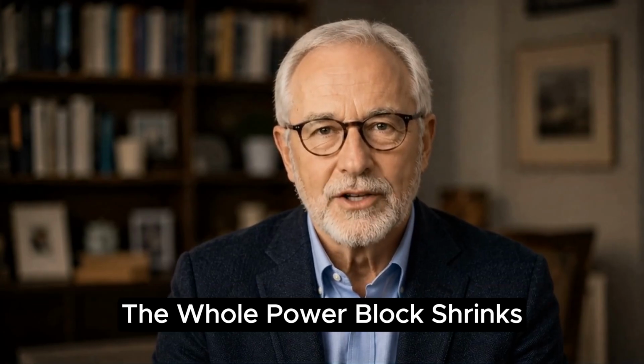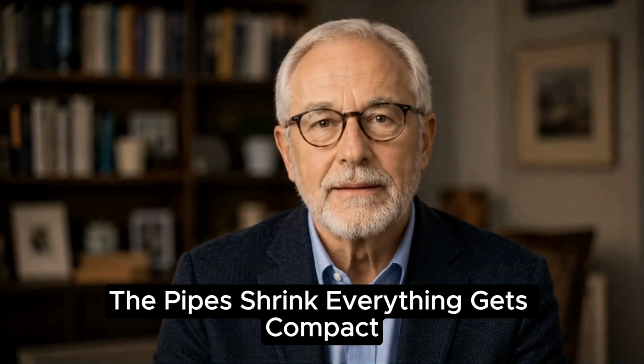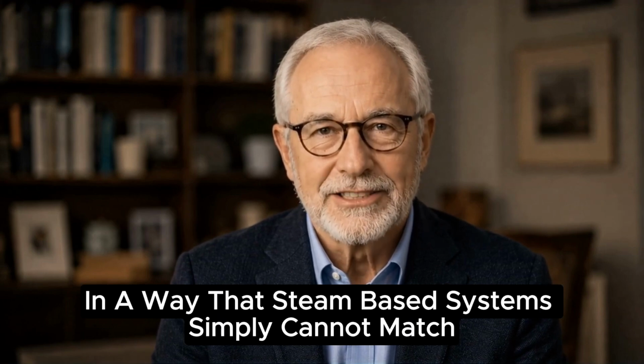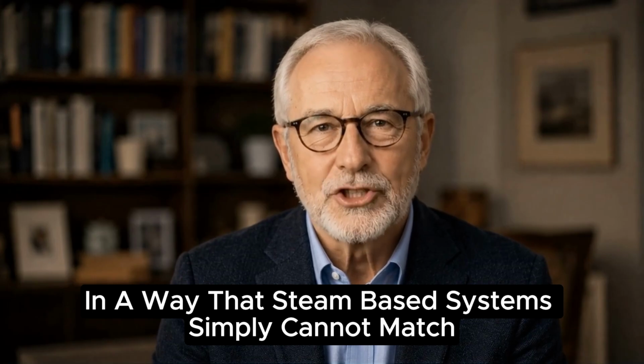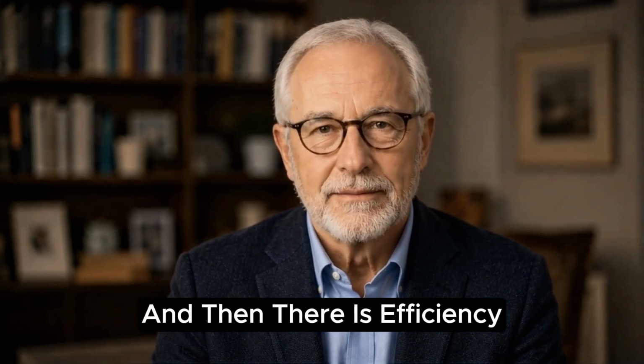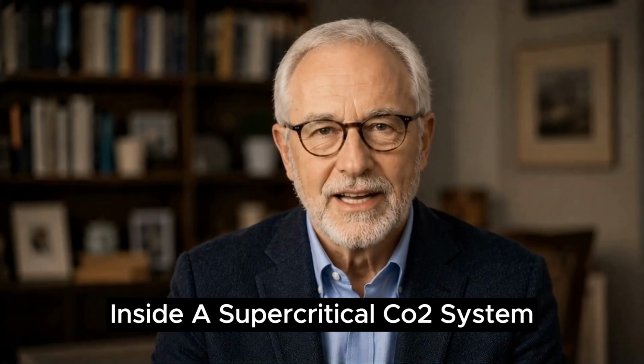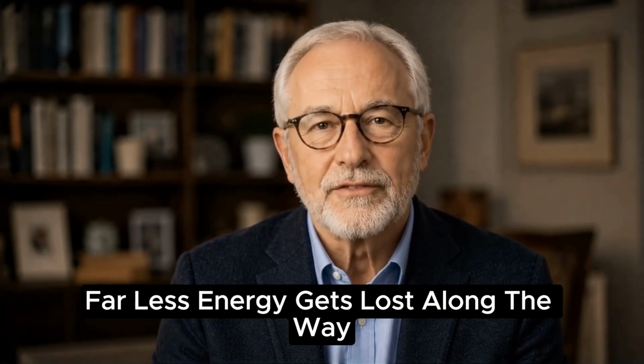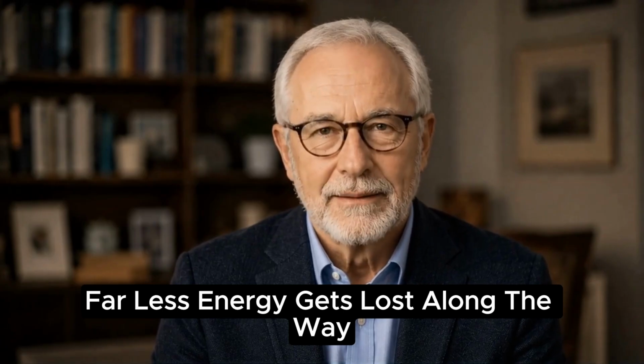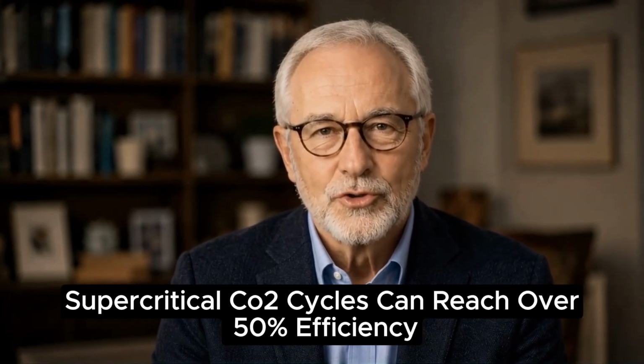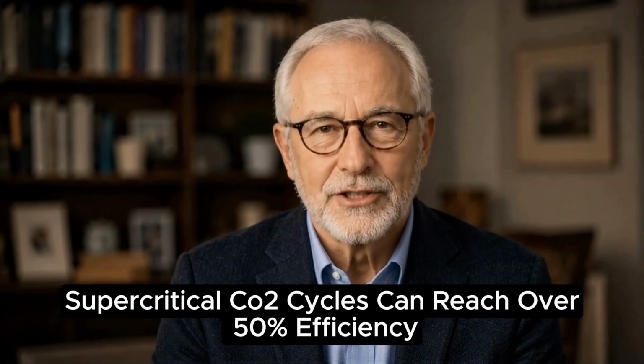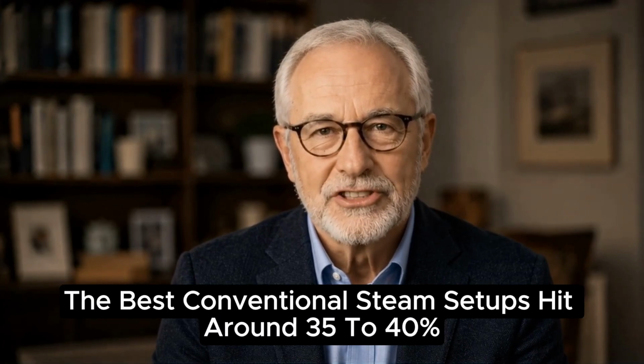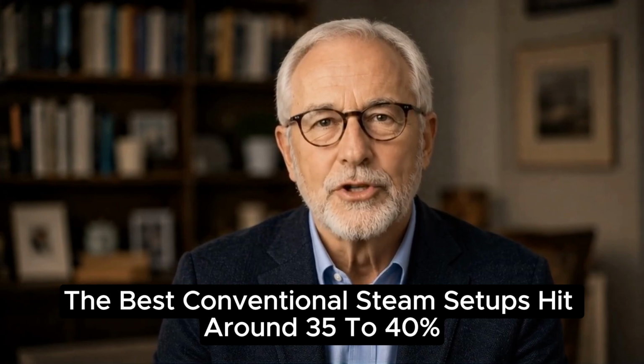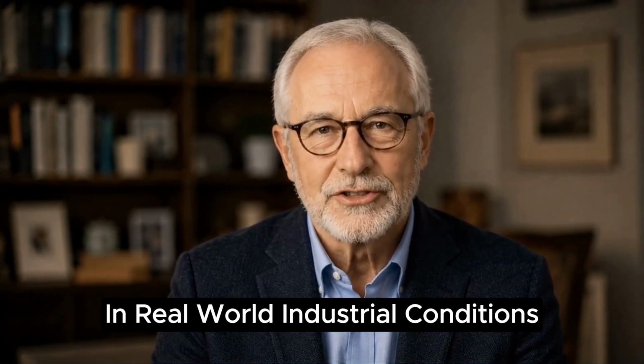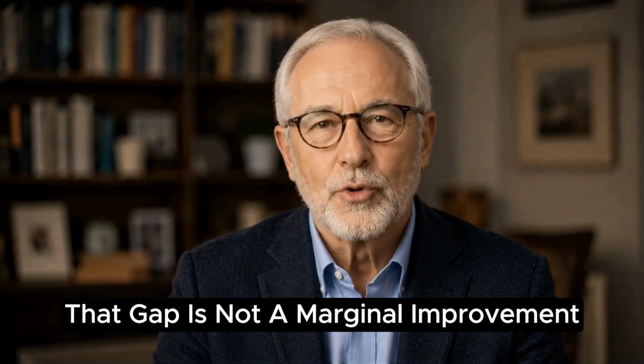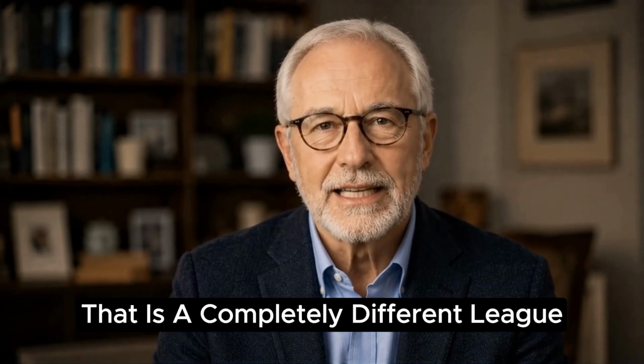That is the physics of working with a fluid that is extraordinarily dense. The whole power block shrinks, the pipes shrink, everything gets compact in a way steam-based systems simply cannot match. And then there is efficiency. The thermodynamics inside a supercritical CO2 system lose far less energy along the way. Well-designed supercritical CO2 cycles can reach over 50% efficiency, while the best conventional steam setups hit around 35 to 40% in real-world industrial conditions. That gap is not a marginal improvement — it is a completely different league.